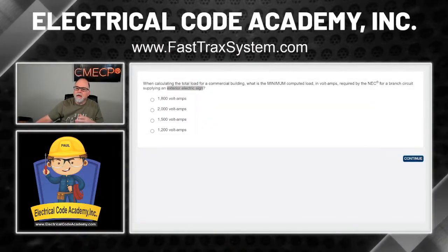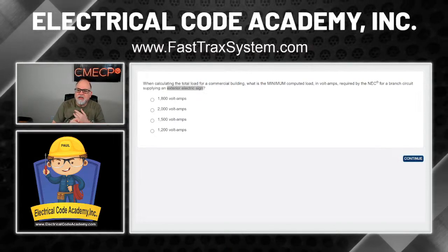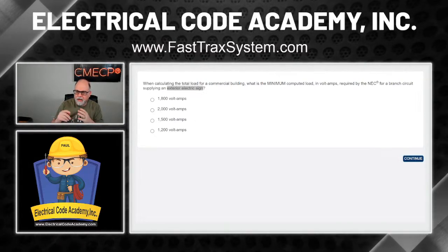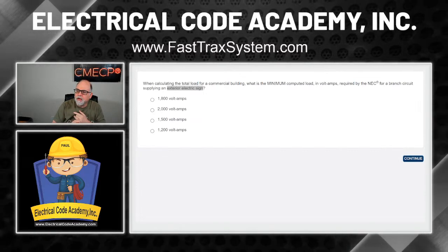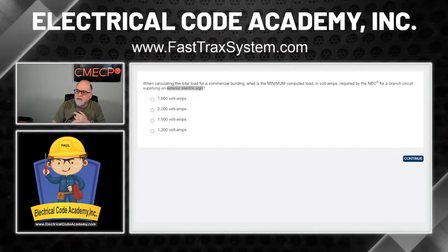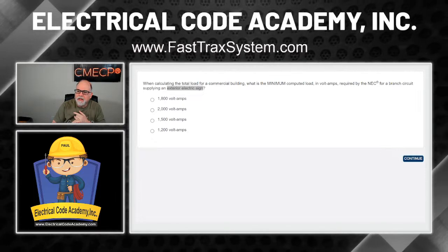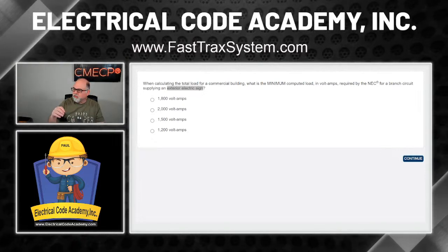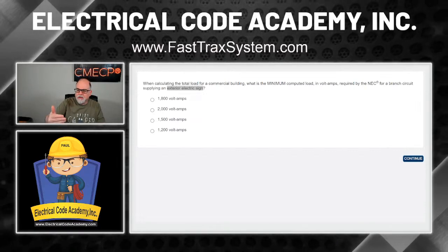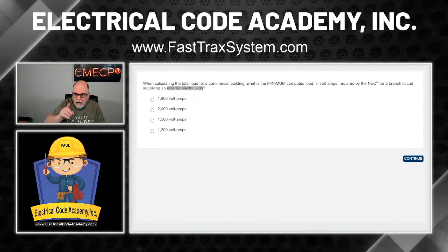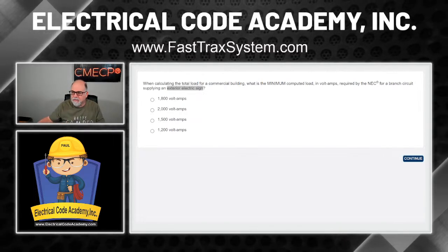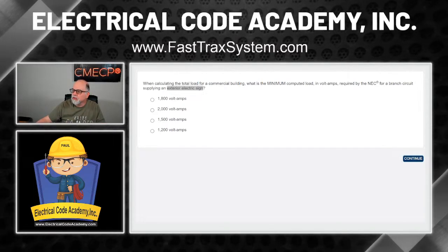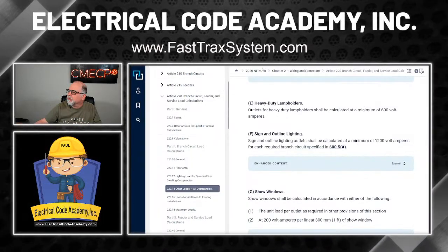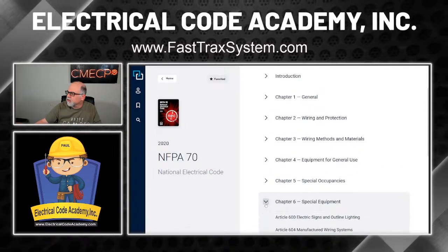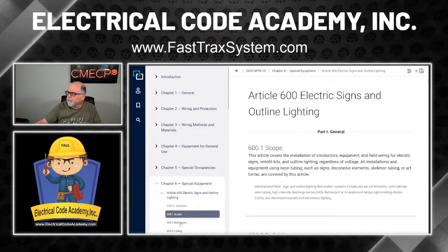All right, so when calculating the total load for the commercial building, what is the minimum computed load in volt-amperes required by the NEC for a branch circuit supplying an exterior electric sign? Okay, so based on this, it looks like that's 1200 VA, and it might be. But while I'm at it, I want to go look at 600.5. I need to go look at it. So let's go look at it real quick. We don't want to get tripped up on anything. So we'll go back here, and I'm going to go to 600.5 real quick.